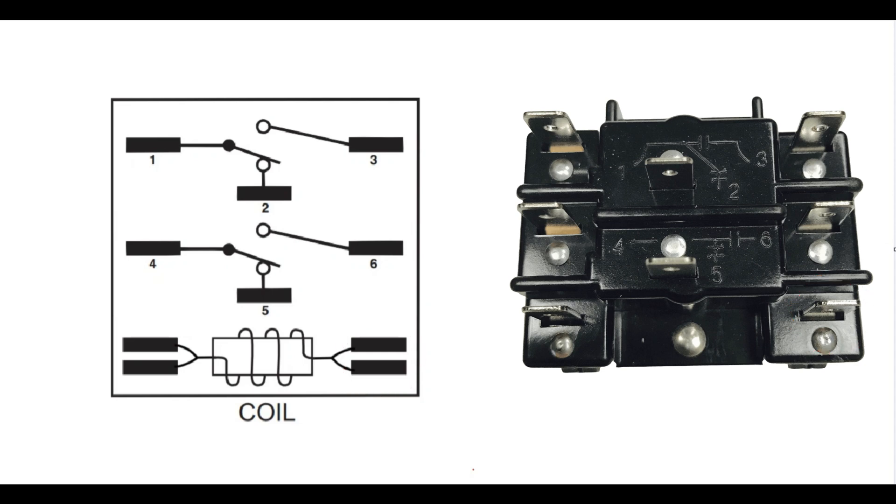So basically how this works is you have what's called normally open and normally closed contacts. Now you can see in this image here, we are in a normally closed position. So this is the position that the relays, the switches inside the relays are in when it comes out of the box. You don't have to add power to it. You don't have to do anything. The springs inside there hold these switches in these positions.